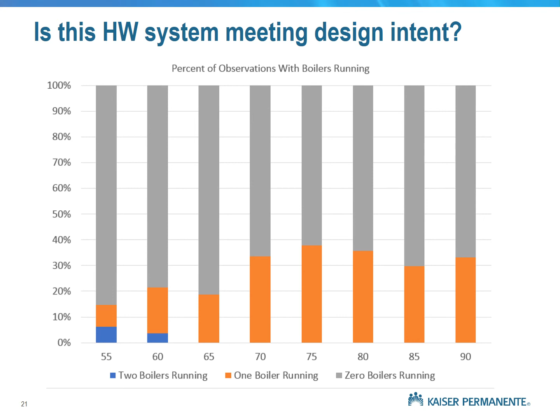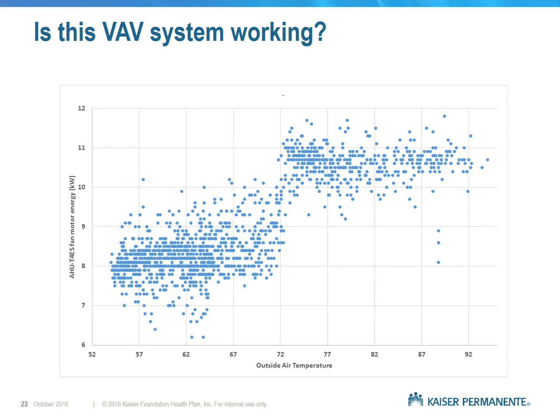What about this? Does this look like a VAV system? As outside air temperature increases, we should see fans running faster, and vice versa. As outside air temperature decreases, we should see fans running slower, right? That doesn't really appear to be the case here. What about this one? Well, that looks more like a VAV system, right? This is the hospital, by the way. This is an OSHPD system, OSHPD VAV. Everything else I'm showing you is B occupancy buildings.